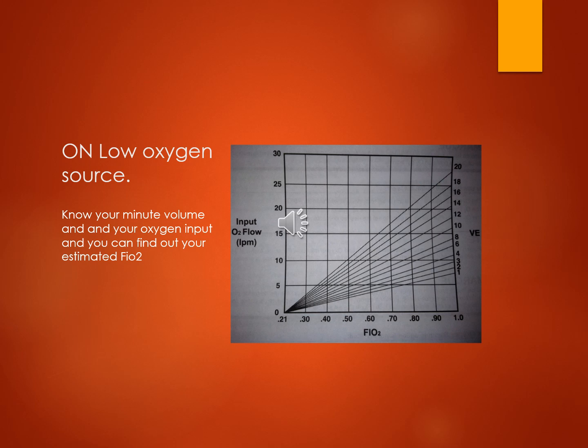Okay, this is what I was referring to earlier when I talked about doing a low flow oxygen into the ventilator through that Christmas tree and an O2 tubing and a flow meter. So you can look on there and say, okay, what would my estimated FiO2 be? Say, let's scroll over and say my patient is doing a minute ventilation of 12, and then follow that over. I'm trying to do it while I'm talking on a microphone. It's not as easy as you think it would be. And then scroll over, so I want them at 15 liters. So what is that going to be? It's going to be about 80%, right?